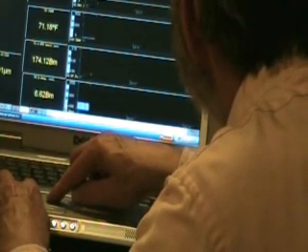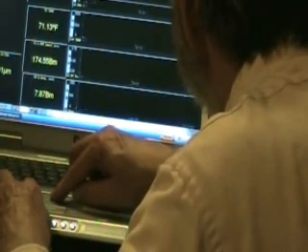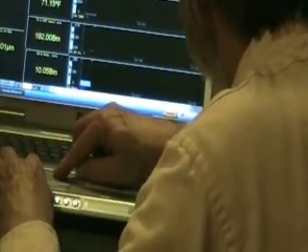So what we have to do is magnify what's on the screen, so that we can see you breathing. Okay, breathe in, breathe out, breathe in. Okay, now we can see a definite change, so we know we're picking up the signal. Breathe in, breathe out. Okay. So there's a good respiration signal. That's working.